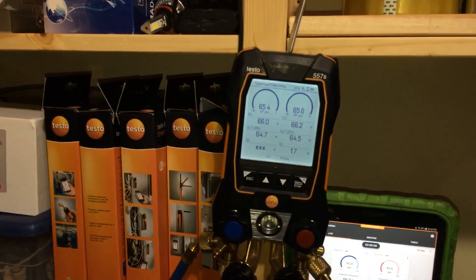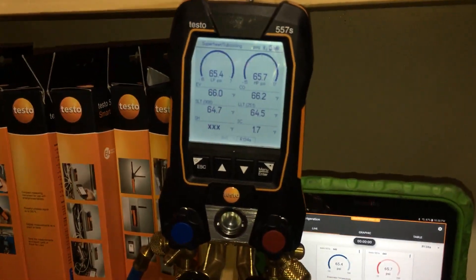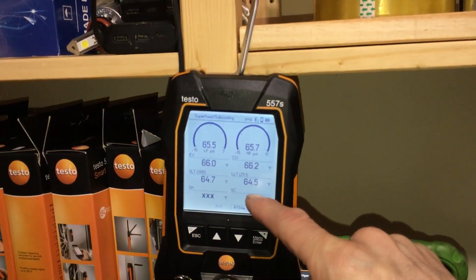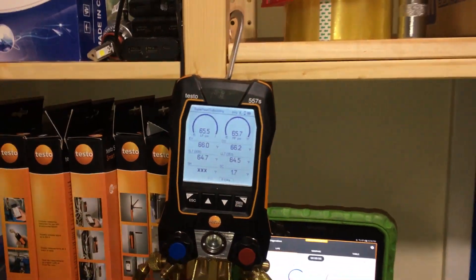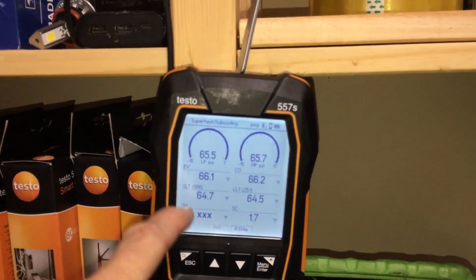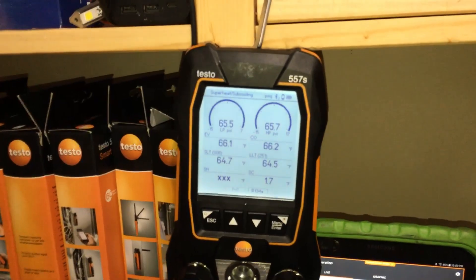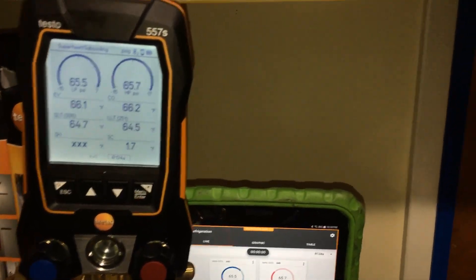When the gauges say 64 degrees, I thought it was 70 in here — it's not. It's 64 degrees in this room because those gauges have been sitting in this room overnight. So it's 64.5 or 7 degrees, as you can see by the temperature gauges sitting down in the box behind me, because those did not come out of my car. The bottle came out of my car, the gauges were inside. So if you went to the PT chart, it would not line up correctly, because the bottle is colder than this room. So this is pure R134, and it should match up — but it doesn't.